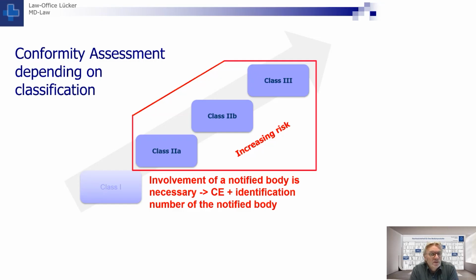And you can see it on the CE mark. Each medical device which is accompanied by a certificate of a notified body has not only the CE mark, but the CE mark is accompanied by the identification number of the notified body. 4 digits. 4 digits as identification number for a notified body. Each European notified body has its own 4 digits, and the CE mark must be followed by the 4 digits of the notified body so that everybody, also the distributor, can check whether the manufacturer has really accompanied its conformity assessment procedure by a notified body and by which notified body.